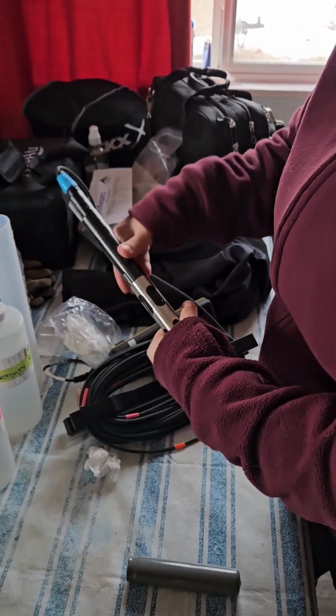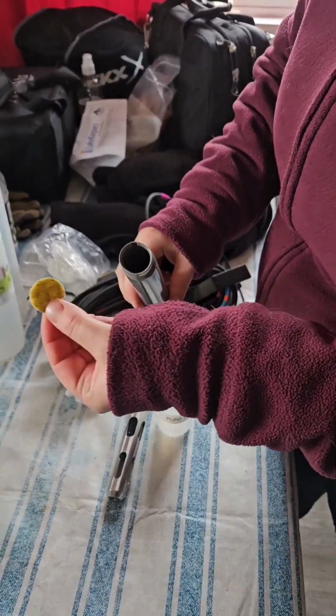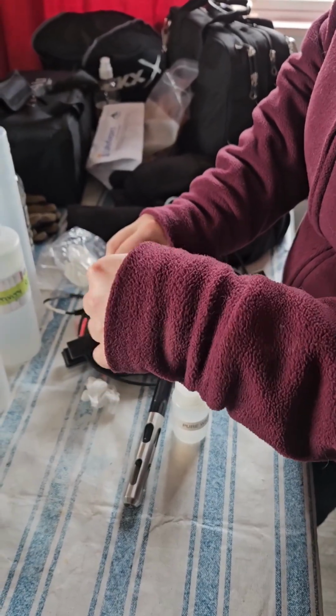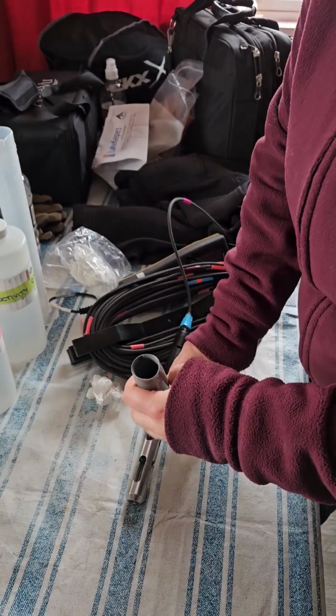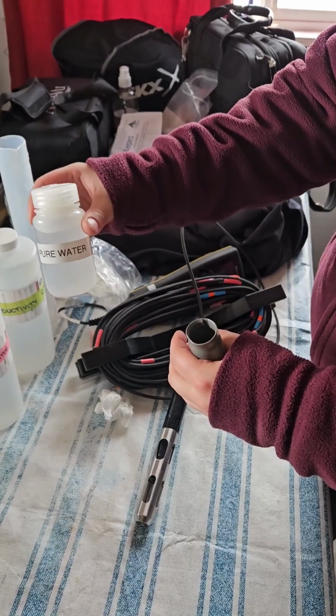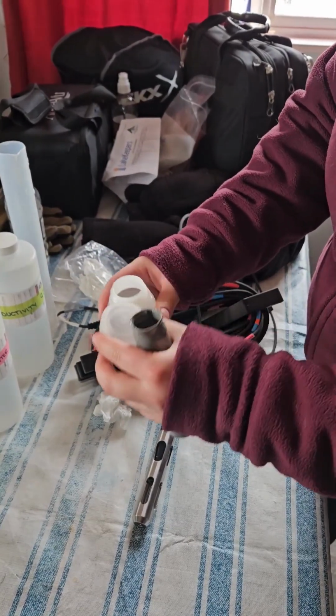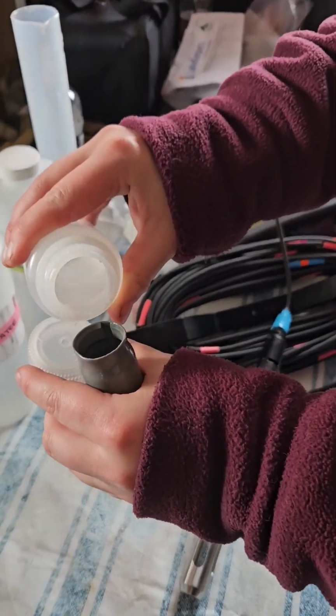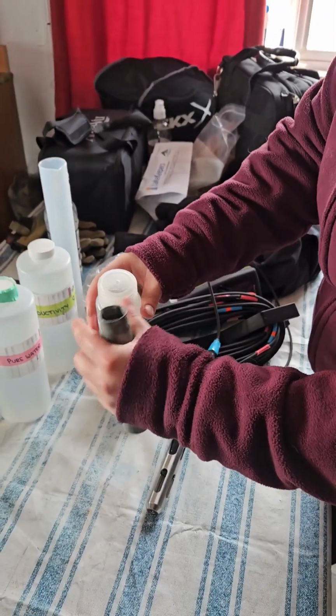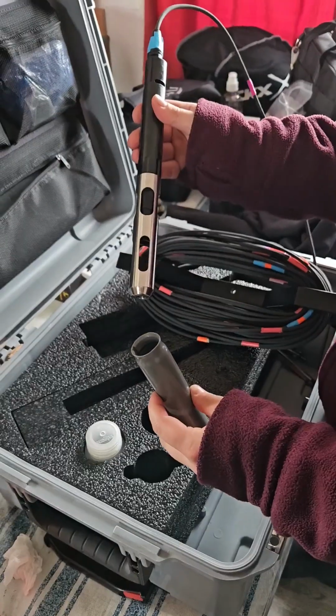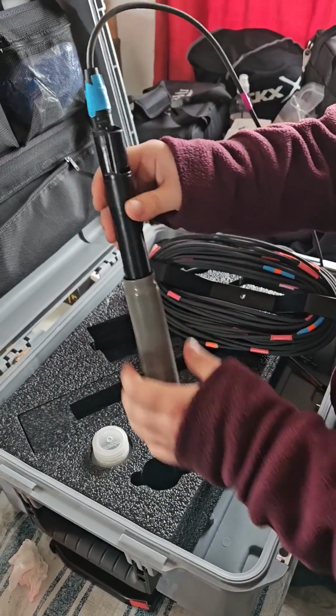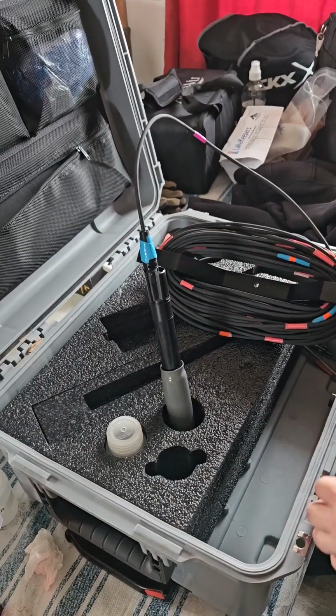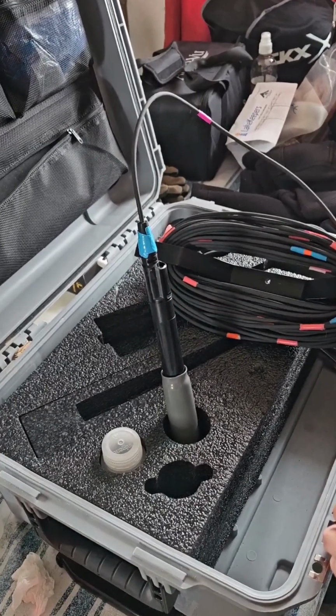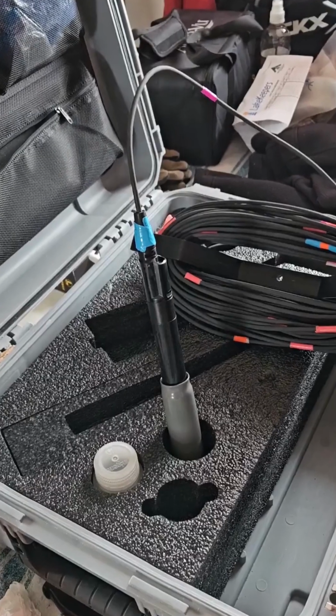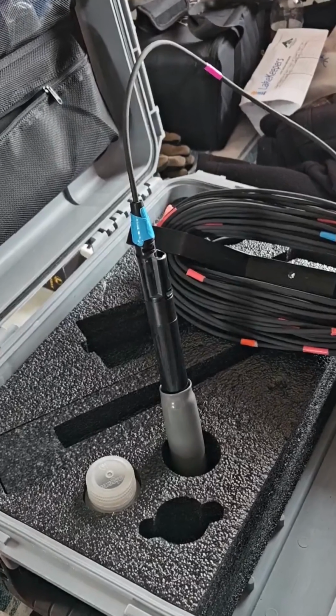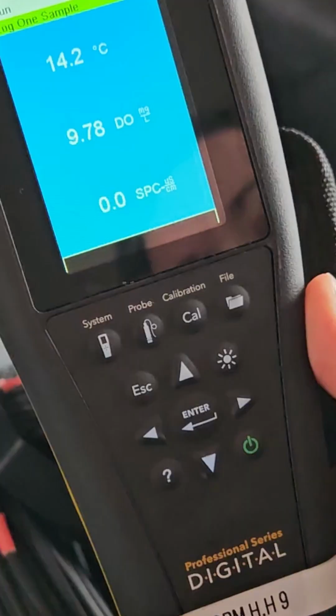And in the gray sleeve will be a yellow sponge that we'll make sure is in there, and we will put some pure water. You don't need a lot, just a little bit, just to wet the sponge. So once that's on, we will put the gray sleeve back on and stand the probe upright while we begin to calibrate. Allow your probe to stand for about a minute just to allow the probe to acclimate to the moisture from the wet sponge.